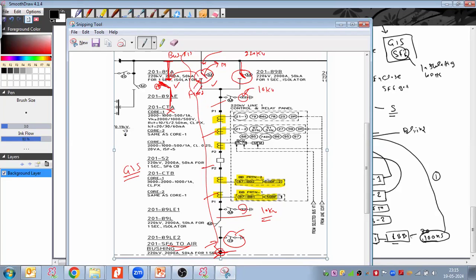So in general, how do we follow, with a breaker or without? It depends; there is no general procedure. For the bus coupler we take a breaker, but for the bus sectionalizer it depends on what is required by the client. As far as high voltage is concerned, like 380 kV? No, it is purely irrespective of the voltage level. How they want to do operations and maintenance, accordingly they will decide. I have seen a CT also in the bus section, sir, along with the breaker. Yes.